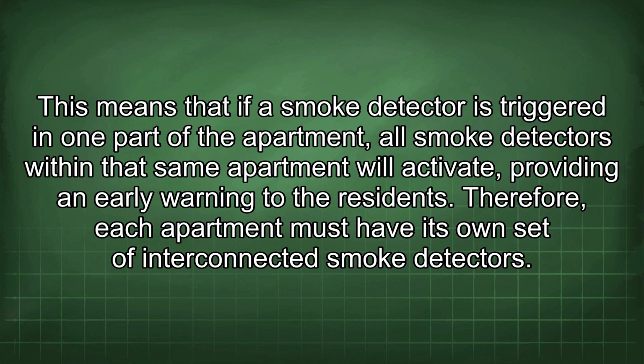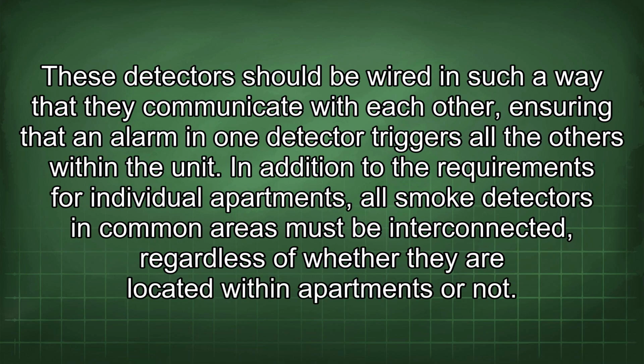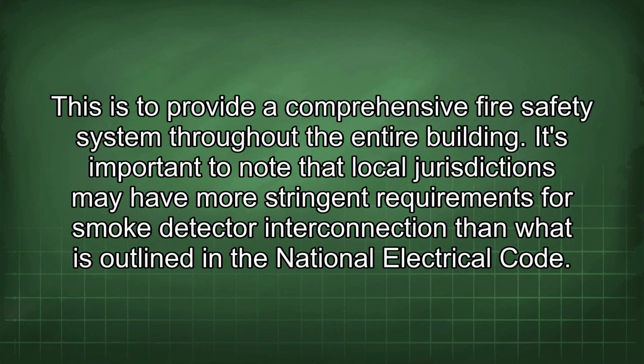Therefore, each apartment must have its own set of interconnected smoke detectors. These detectors should be wired in such a way that they communicate with each other, ensuring that an alarm in one detector triggers all the others within the unit. In addition to the requirements for individual apartments, all smoke detectors in common areas must be interconnected, regardless of whether they are located within apartments or not. This is to provide a comprehensive fire safety system throughout the entire building.